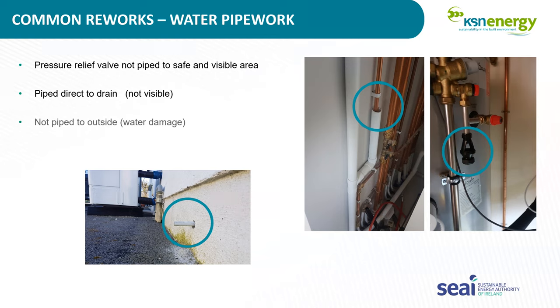Typically, on the image on the rightmost side, what we would say is that if there's a tundish and someone could see it, it just means they can see a drip coming from the safety valve. But unfortunately on that one, they haven't piped it to anywhere. So I can only assume from that picture that it's located indoors. So if something happens, there's going to be water damage and it's going to flood the place. So they're the key things when it comes to the safety valve.